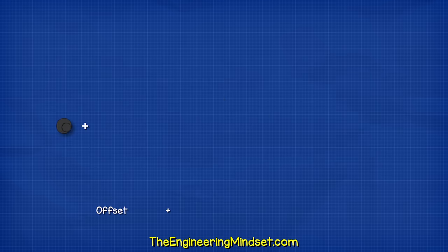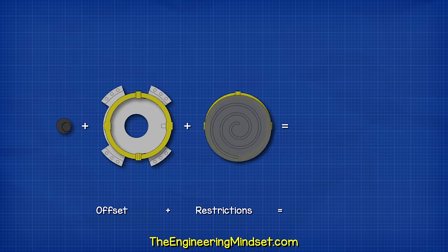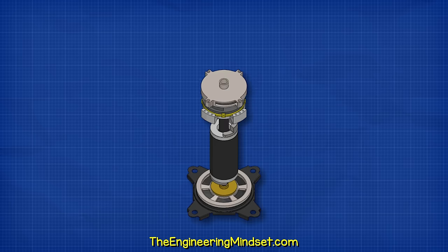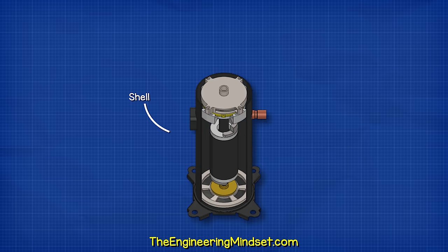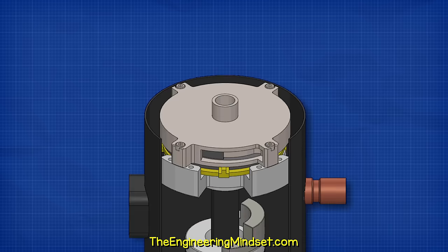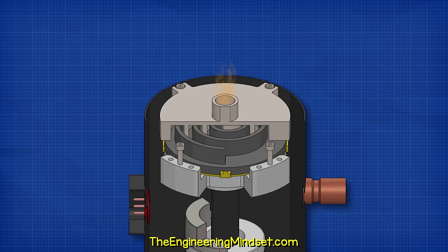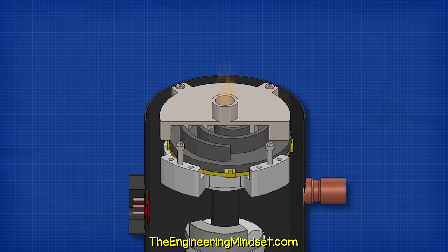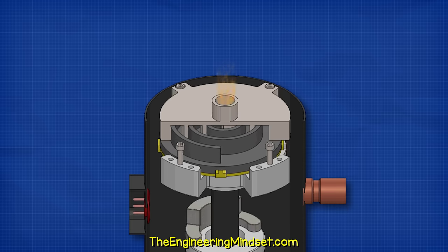The offset of the shaft, combined with the restrictions of the Oldham ring, allows the scroll to orbit without rotating on its axis. The orbiting scroll will sit within a fixed scroll. This is connected to the shell and also the housing, and so this is locked in position. When the shaft rotates, the orbiting scroll will now move within the fixed scroll. This causes compression.